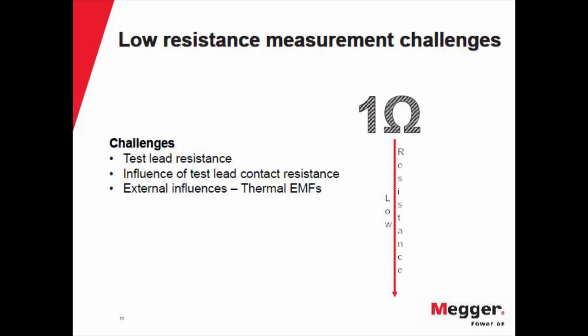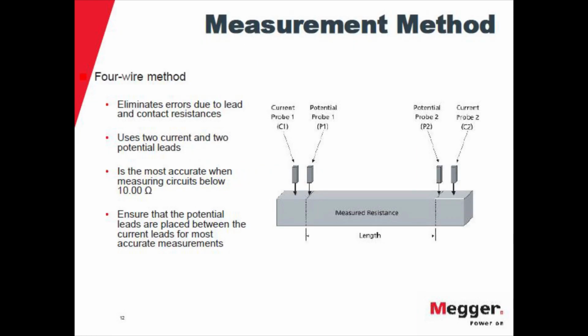The different places where you can apply this: motor windings, circuit breakers, we already mentioned that, switches, welds, coils, batteries, straps. There's a challenge when measuring a low resistance. First of all, you might test the lead resistance, so you need to know how to use the leads appropriately to not influence your result from the lead connection. And you can also have external influences, like thermal effects or electromagnetic influence, and additional current that might be circulating if you're doing a test on a battery, for example.